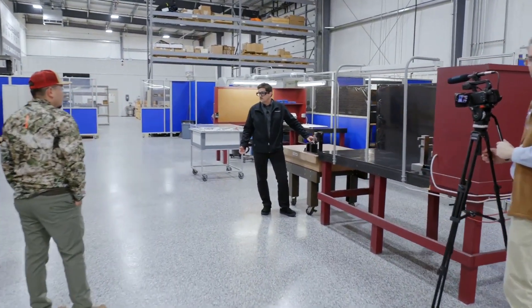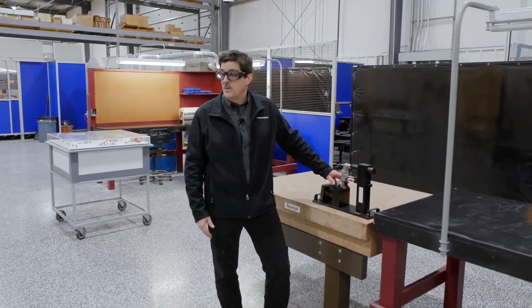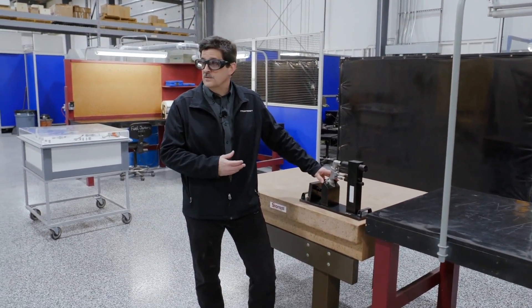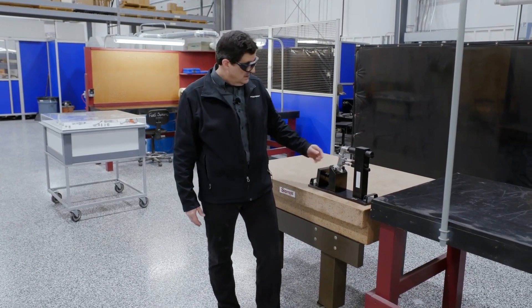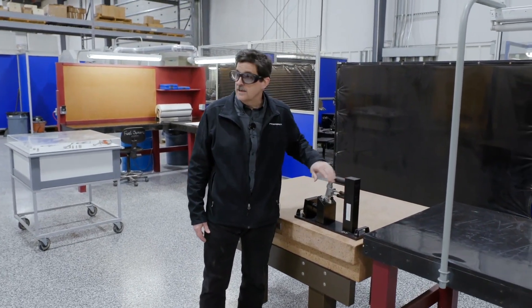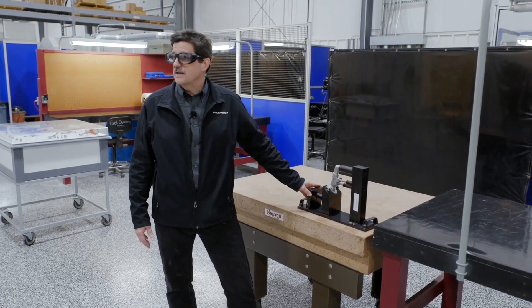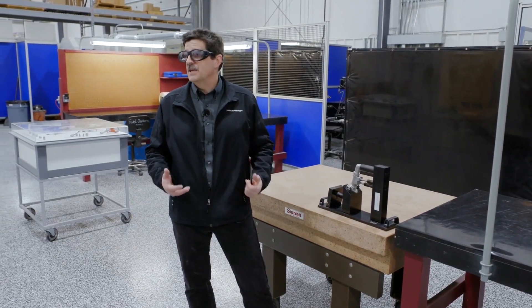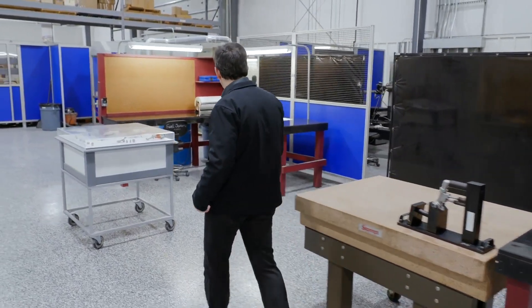What's unique about what we do here is we can overhaul dual fuel nozzles. We also overhaul the whisper or water injection nozzles and the sprint nozzles, but we also make sprint nozzles new and make dual fuel nozzles new. We have the forgings for the main body and all the parts to construct an entire nozzle. This simple fixture allows you to confirm and check every single interface position with the engine, so each nozzle can be verified to ensure there won't be any interference fitting it into the engine when completed.